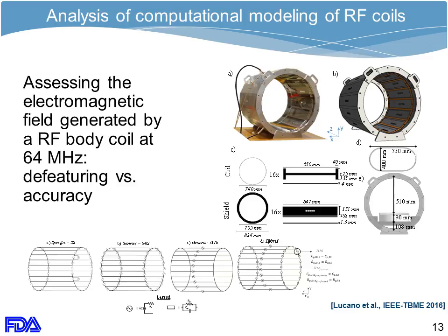RF heating depends on several variables, and mostly we can categorize them as three main parameters. There is the source of the radiofrequency field, which is the coil, as you're seeing here. There is the patient itself, that's the load of the coil. And for CDRH, another aspect is additional medical devices that may be implanted in the patient. So I'm going to go through examples of each of these three categories.